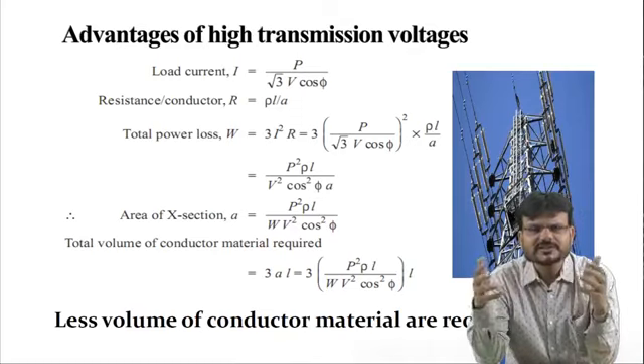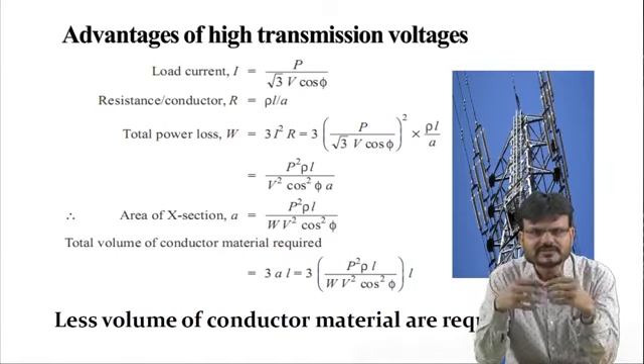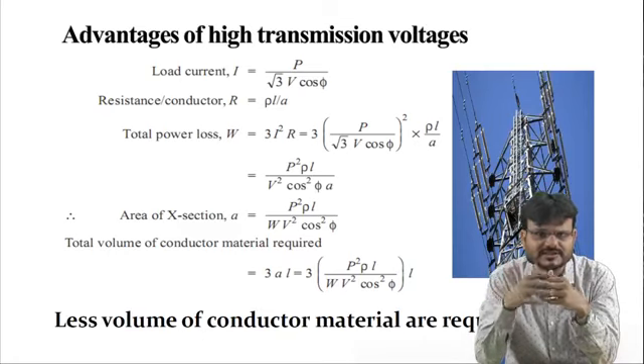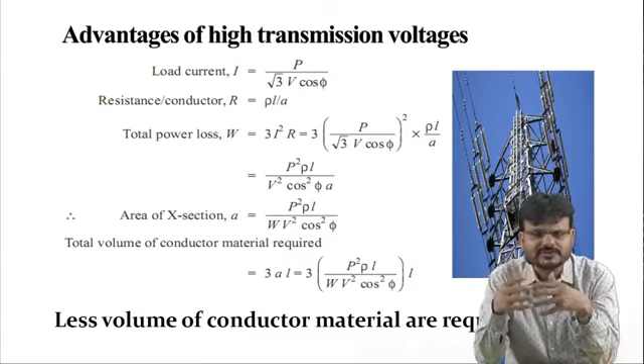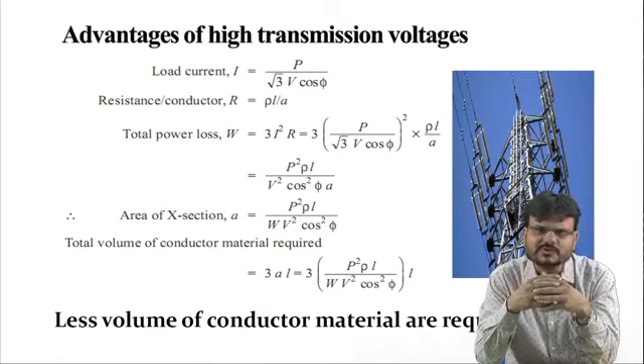Because you are using a three-phase, three-wire system, we have to see how much loss you are able to reduce with high voltage. So the loss is equal to I square R, because you are talking about the three-phase three-wire system. So the total power loss is equal to 3I square R. And R can be replaced with the formula, as you know, R is equal to rho L upon A. L is the length of the conductor, A is the cross-sectional area of the conductor.